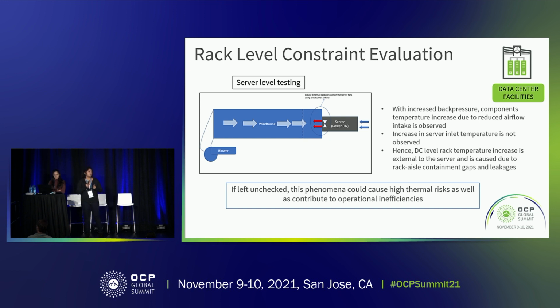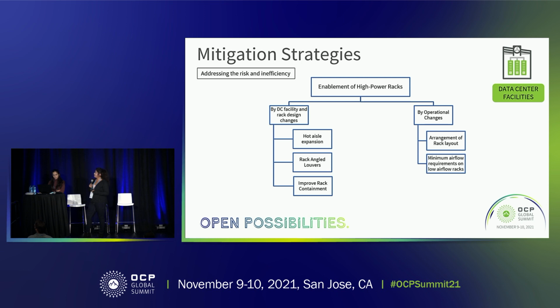So if this phenomenon is left unchecked, it could cause an increase in inlet temperatures for our racks. And it could also cause inefficiencies because now we are running the servers hotter, the fans are going to ramp up, and there would be an increase in the power, and that is basically due to a thermally induced phenomenon and not because of a productive workload demand. So we looked at some mitigation strategies by design changes at data center and rack level, or via operational changes to address these risks.